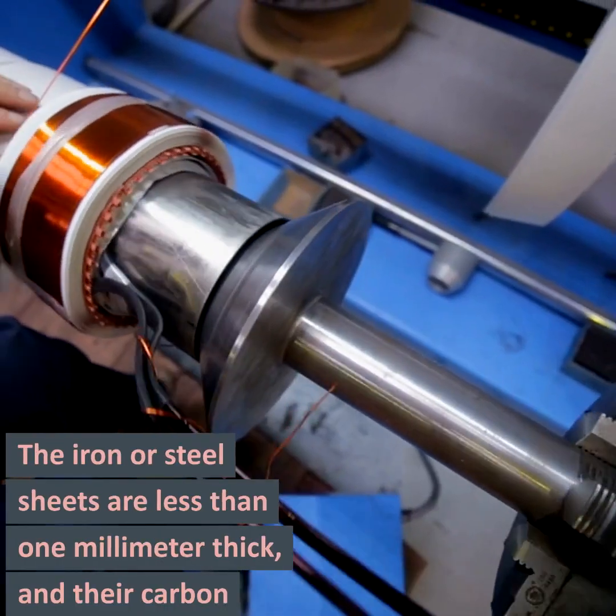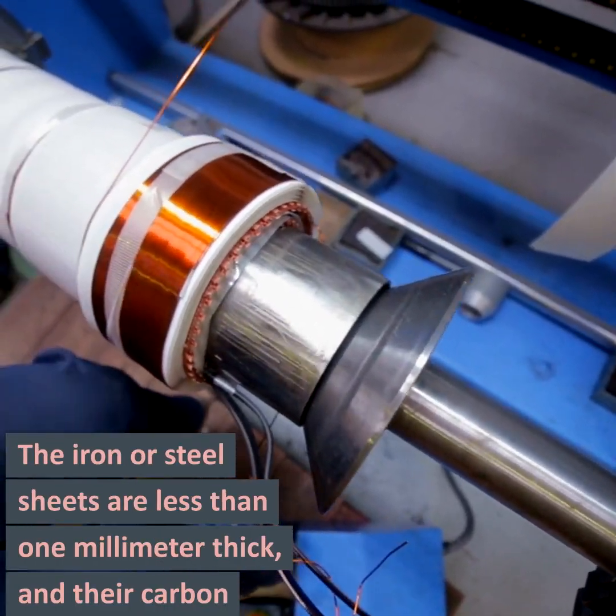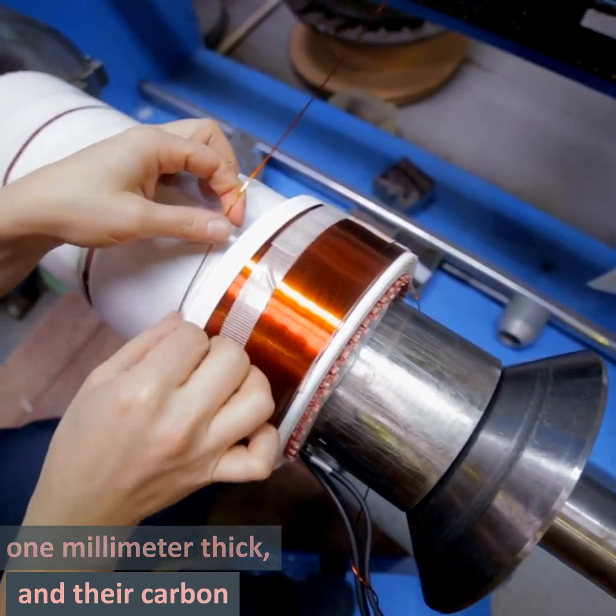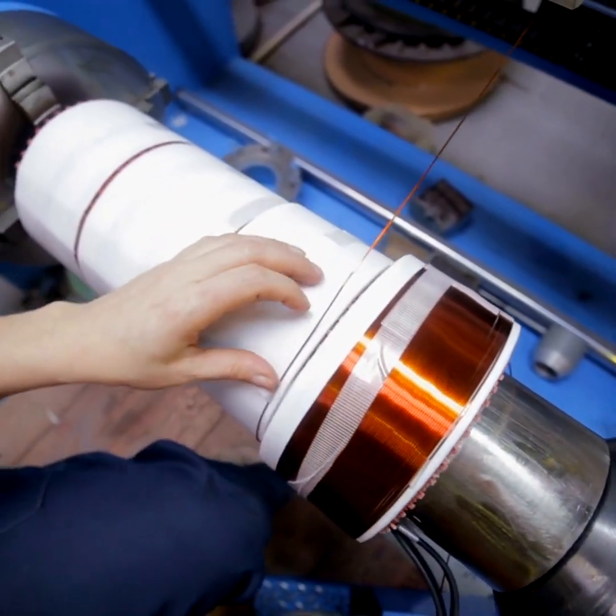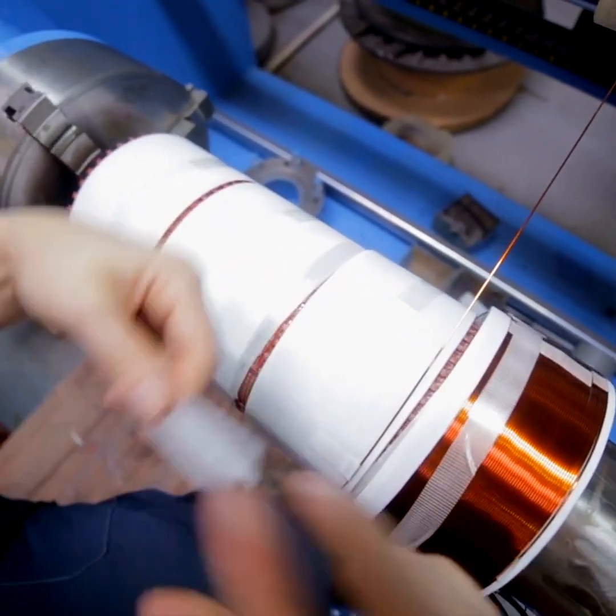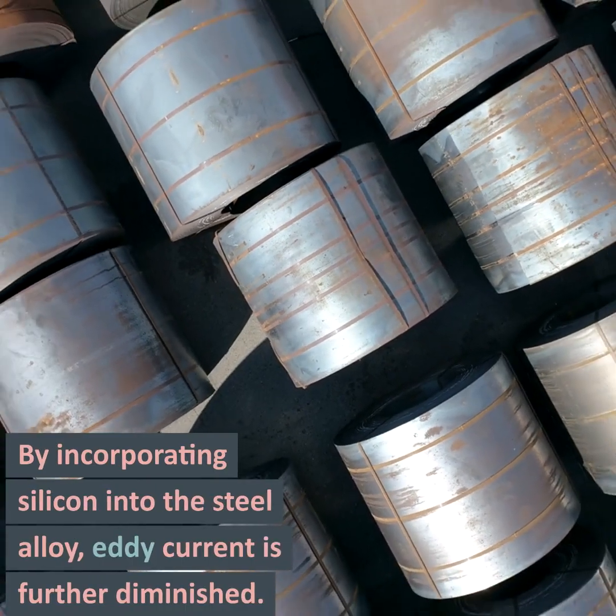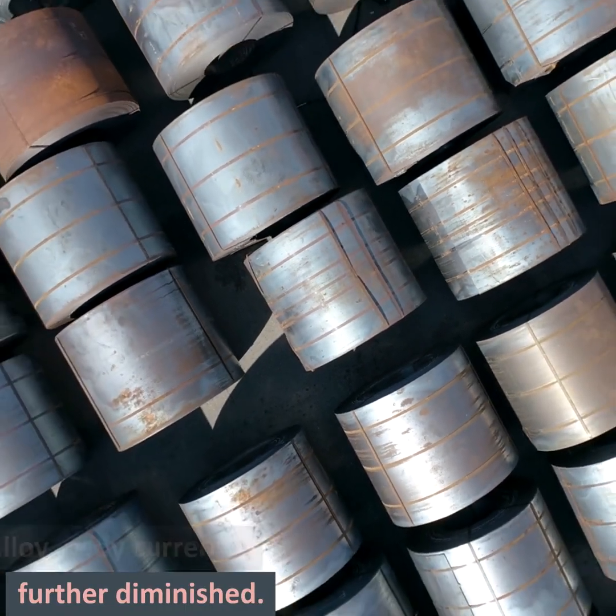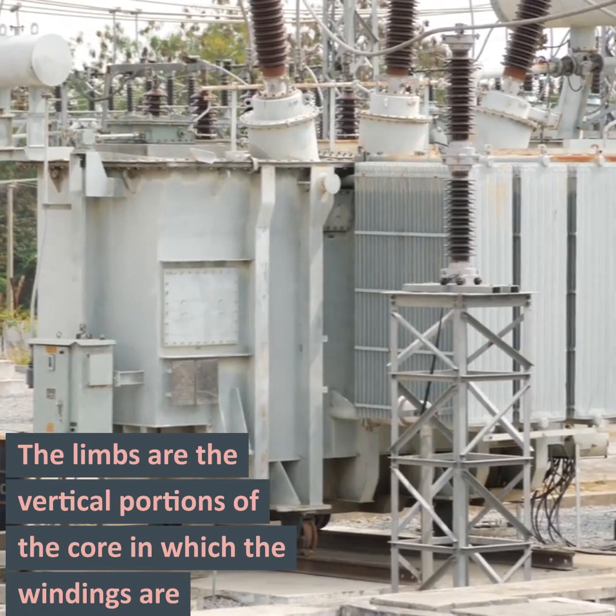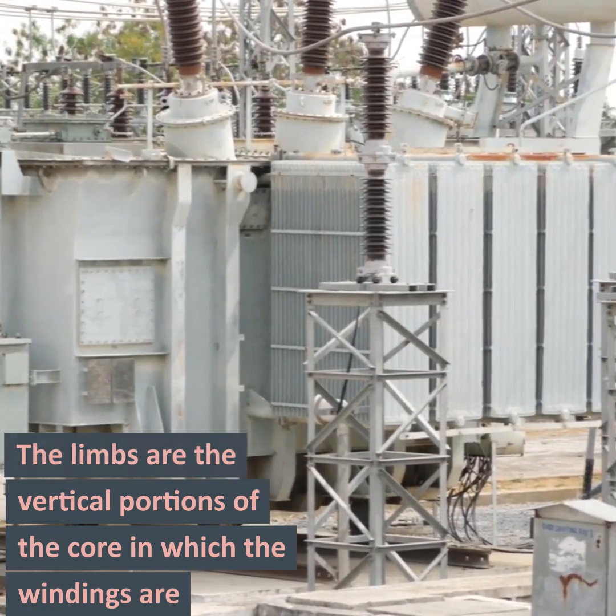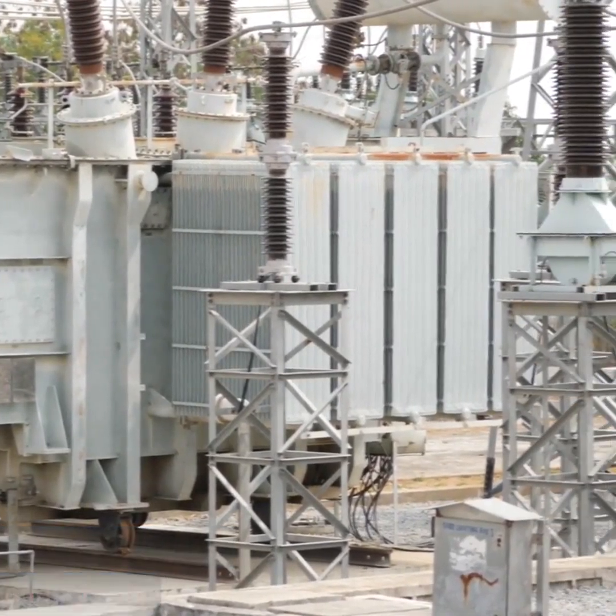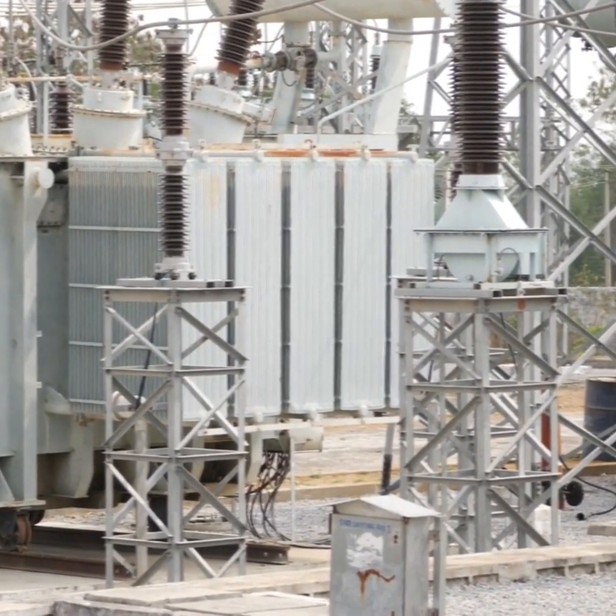The iron or steel sheets are less than 1 mm thick, and their carbon content is kept below 0.1% to minimize hysteresis losses and eddy current losses. By incorporating silicon into the steel alloy, eddy current is further diminished. The limbs are the vertical portions of the core in which the windings are carried, and the yokes are the horizontal portions of the core that connect the limbs.